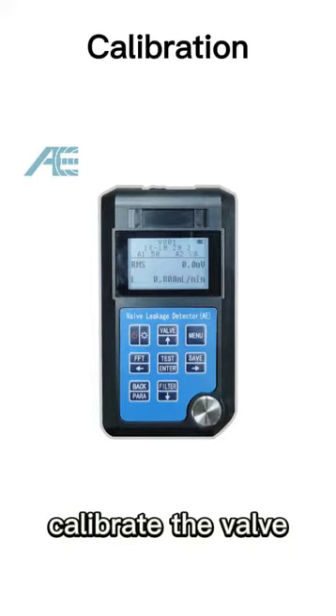If the users have calibration environments, they can calibrate the leakage rates of the specific valves using a sensitive microflow meter. By calibrating the acoustic emission parameters under different leakage rates, the detector can generate a calibration curve which can be used as the reference leakage rate value. First, couple the sensor to the valve. Use the couplant in between the valve and the sensor and use tapes to tie the sensor in place.